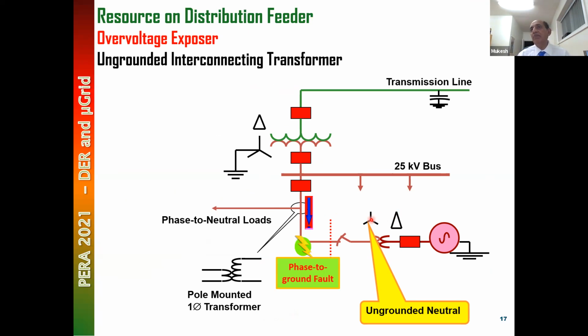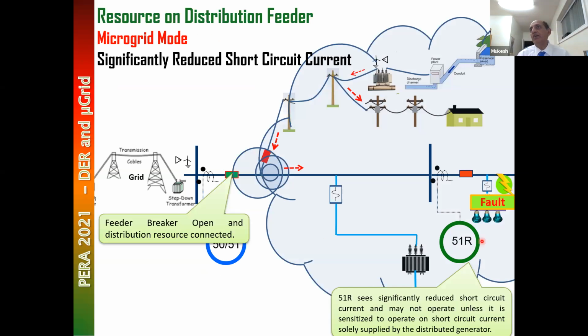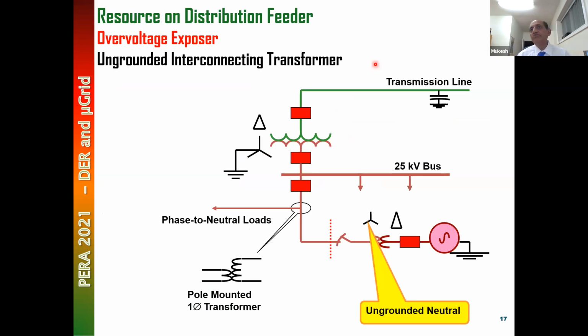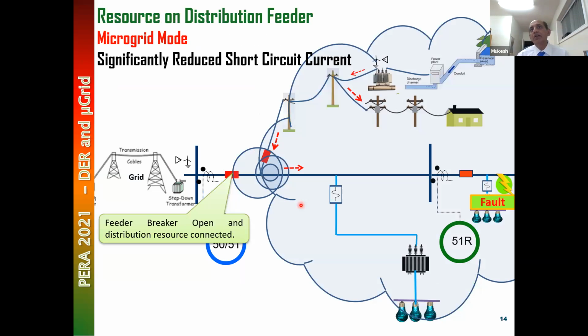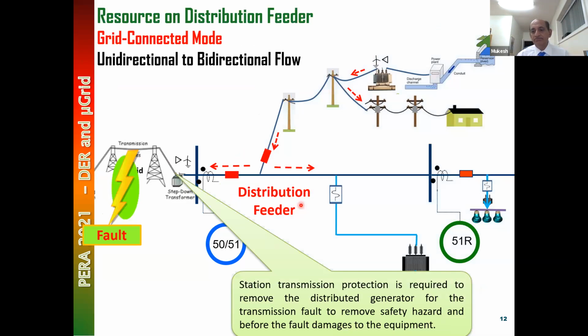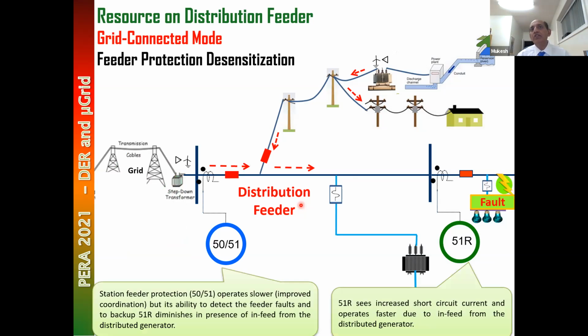If we leave it ungrounded and there's a short circuit, for example here or anywhere in this feeder, as we saw in the earlier example, the same short circuit. Now this ungrounded transformer will not supply any ground fault current, because it is an ungrounded system. Only the short circuit current comes from the grid side. The protection here, that 51 protection on the station that we are talking about, sees the fault, and since no current comes from the ungrounded side, only ground fault current comes from here, and this protection will operate and open the circuit breaker. That's what I'm talking about.